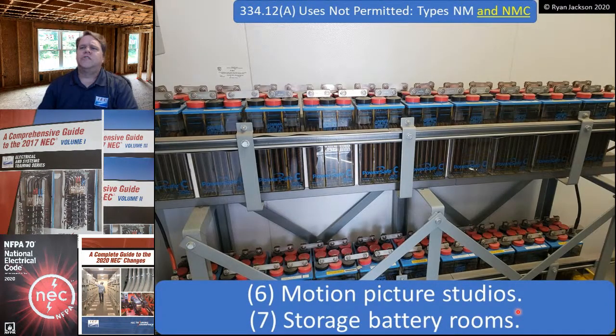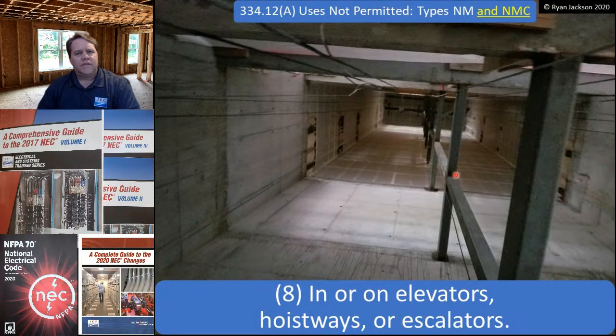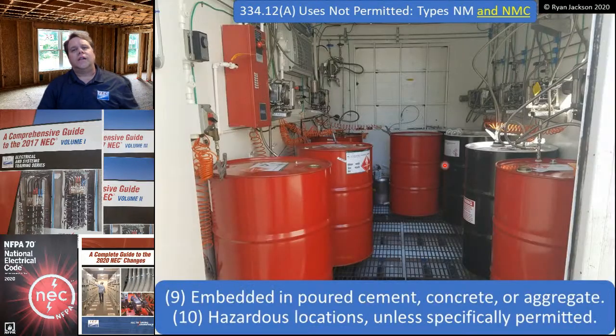We can't use it in motion picture studios or storage battery rooms. Can't use it here in the storage battery rooms. You cannot use it in or on elevators or their hoistways or escalators. So inside of the elevator hoistway here, no NM cable. You're not allowed to embed it in poured cement, concrete, or aggregate. If you need to do that, then I would suggest you buy UF cable. And then, of course, item 10, hazardous locations, unless specifically permitted. Yeah, I mean, this is a place in Virginia, this is the Continental Auto Place, where they test fuel injector systems. So very much a Class 1 location. I mean, this is one of the few actual legitimate Class 1 Division 1 locations that I've been in, where you walk in there smoking a cigarette, it blows up.